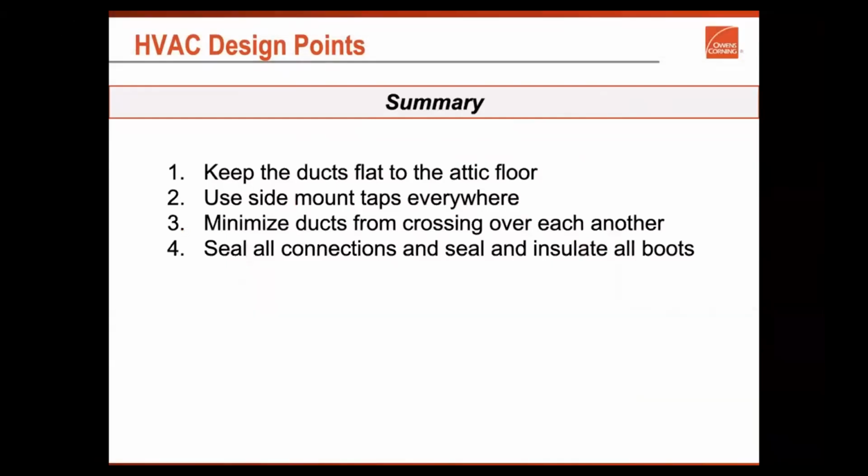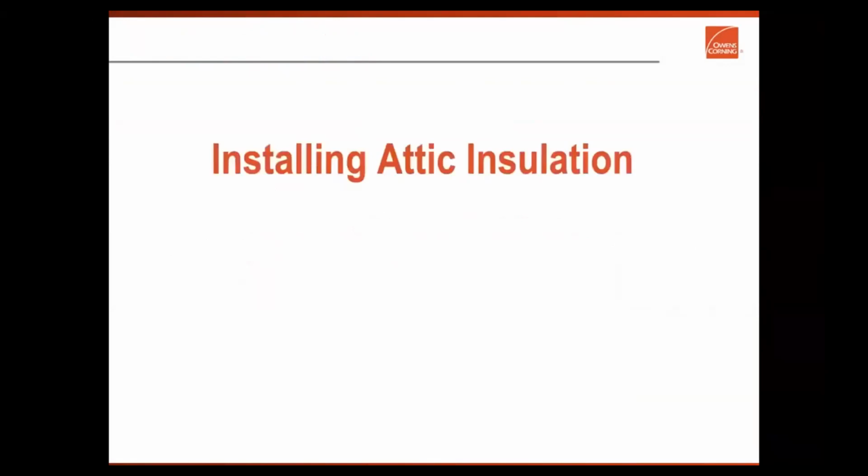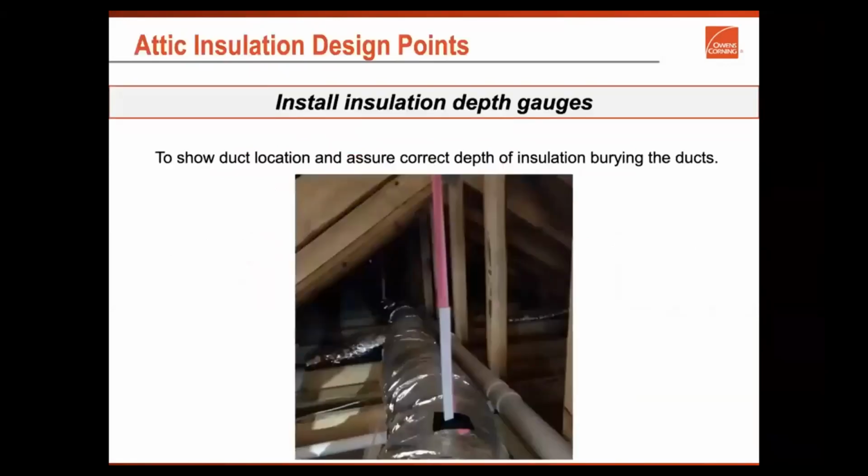So one of the things that we want to do is keep ducts flat in the attic, use side mount taps everywhere, minimize duct lengths, reduce the option of crossing over, seal all connections, and insulate the boots properly.